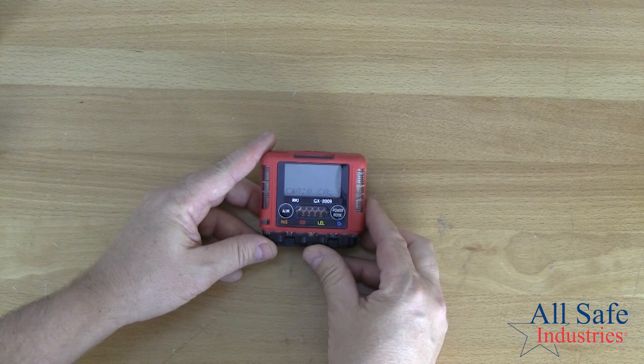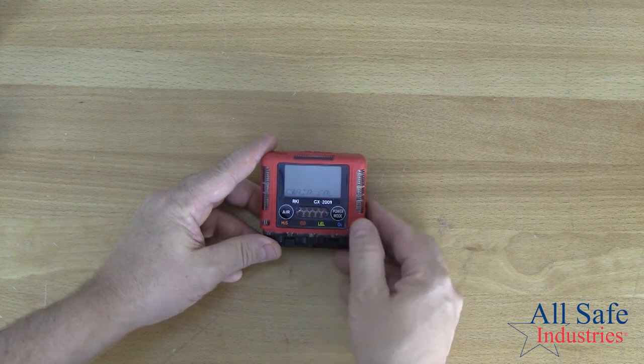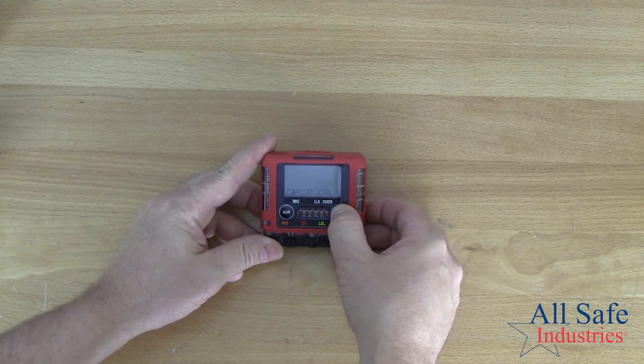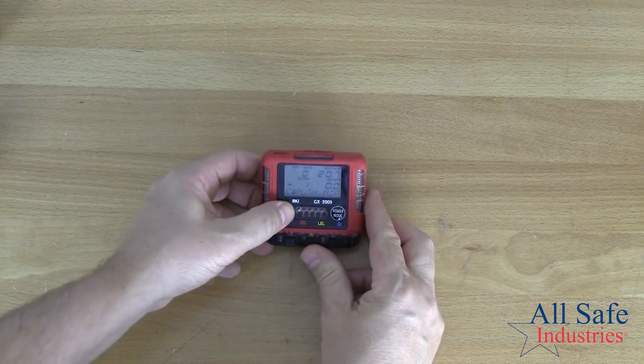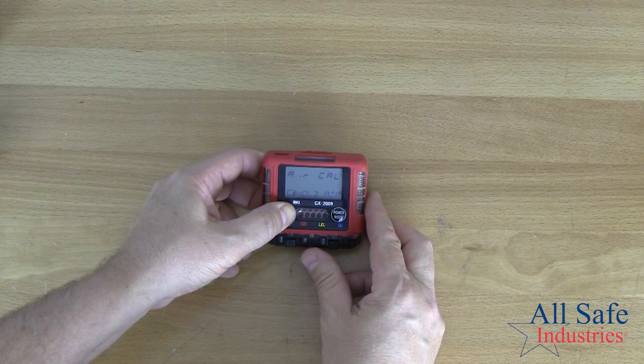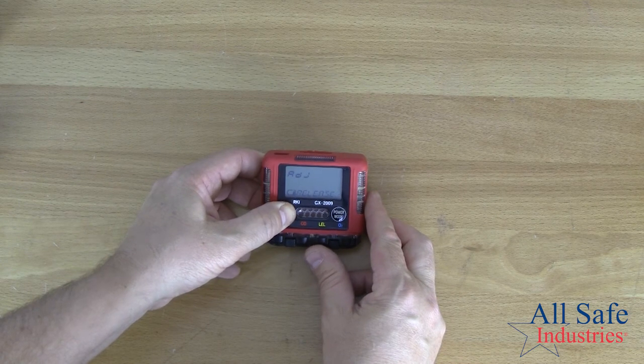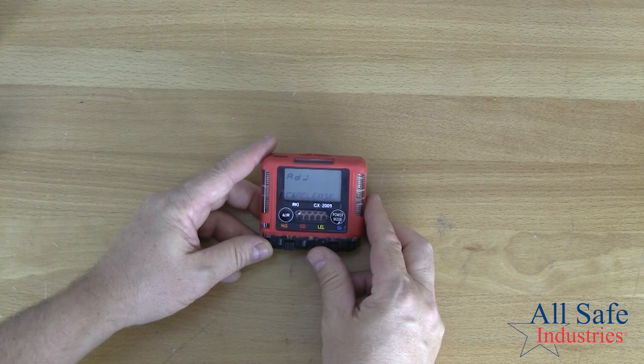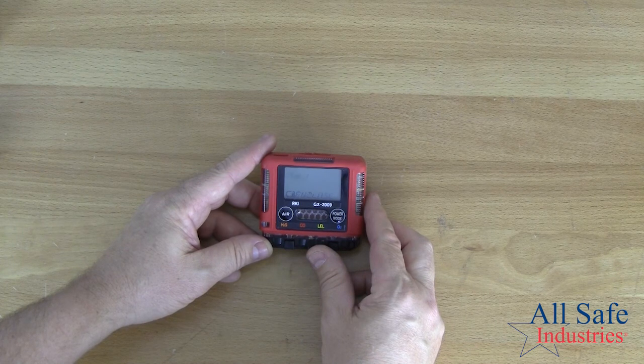So it's always a good idea to start with a fresh air calibration if you hadn't done that already. So let's go ahead and do one. Press your power mode to select air cal. It's telling me push air, so I'm going to push air. Now it says hold air. I'm going to keep holding. And now it says release, so I'm going to let go. And now it says end. And it goes back to the fresh air cal menu. Now we know the sensors are fresh air caled.